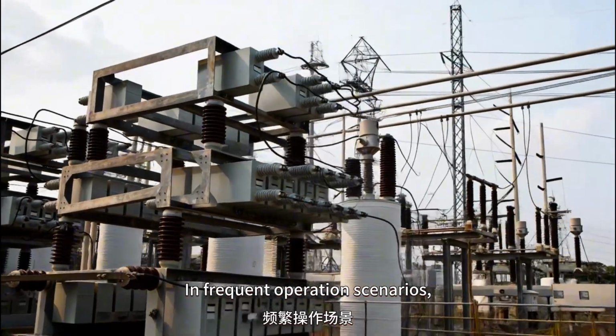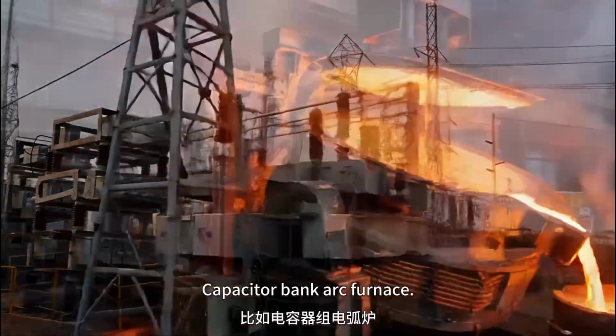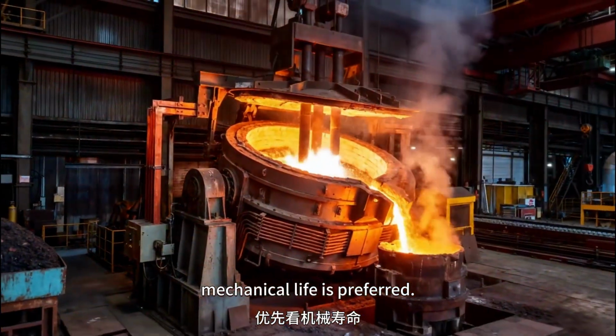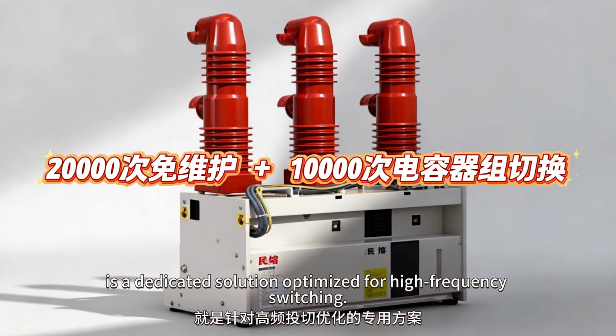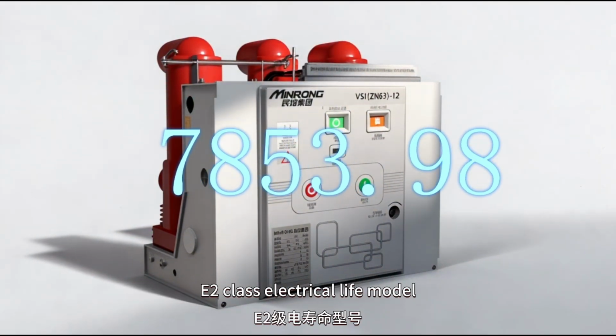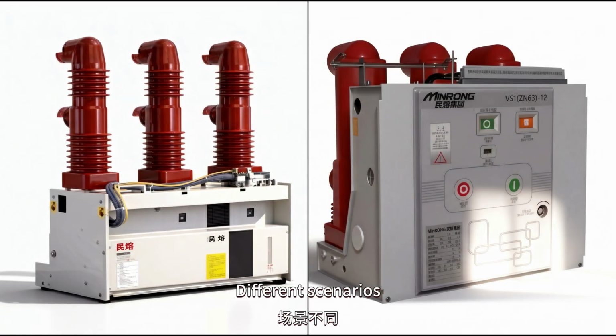In frequent operation scenarios, such as capacitor banks and arc furnaces, mechanical life is preferred. A dedicated solution optimized for high-frequency switching is the choice there. For high-performance requirements, choose the one with 100,000 cycles and an E2 class electrical life model. Different scenarios, the selection logic is also different.